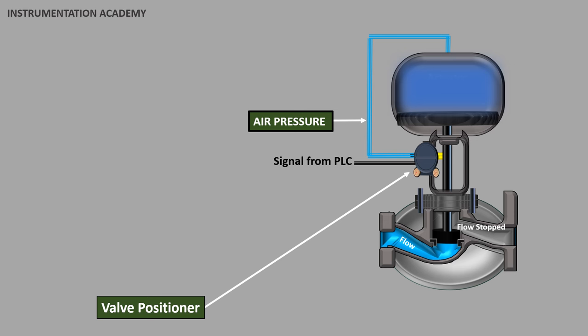If there is no positioner, the pneumatic control signal goes directly to the actuator. As there can be other forces acting on the valve stem, the accurate positioning cannot be achieved.